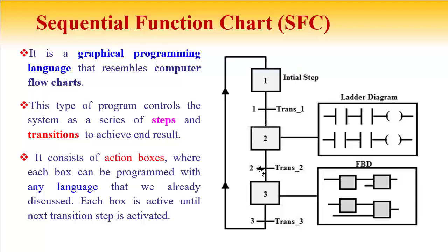The SFC starts from an initial step and ends, then loops again. Between start and end, different steps and transitions are present. The first block is the initial step, followed by Step 2 and Step 3, with transitions between each. These steps can be thought of as sub-programs, and each sub-program can be written in different languages — for example, Step 2 in Ladder Diagram and Step 3 in Function Block Diagram.